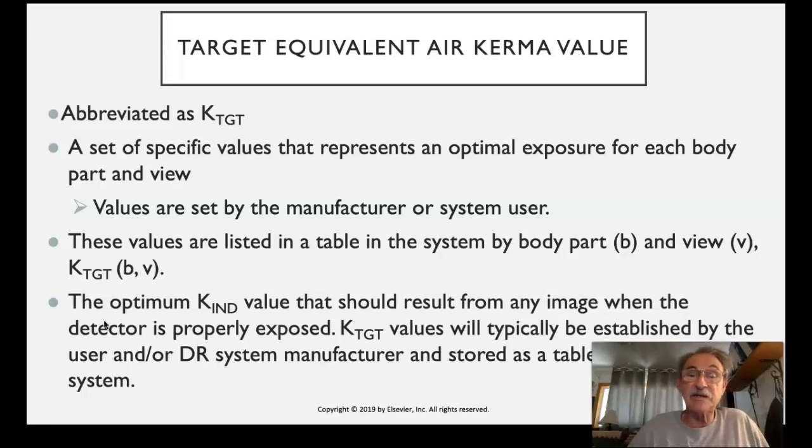Understand that exposure index number is not a specific number. It is not 550. It is a range of numbers, like for instance, between 100 and 200. Any exposure index between 100 and 200 is considered within exposure index tolerance.